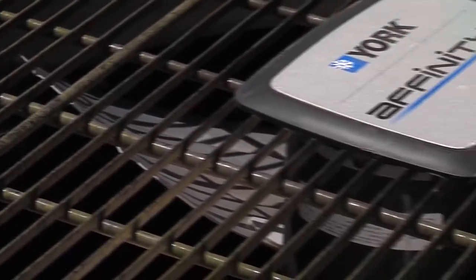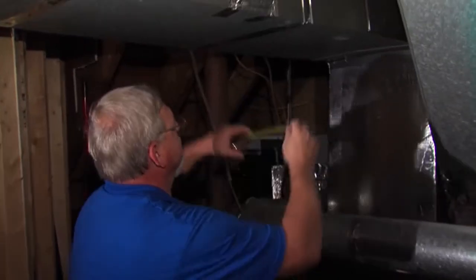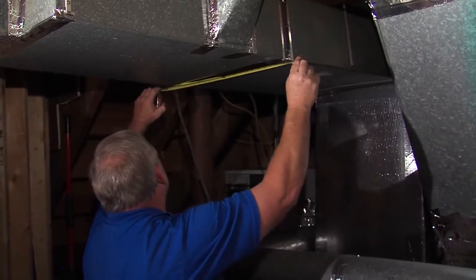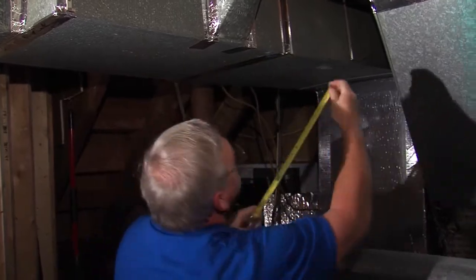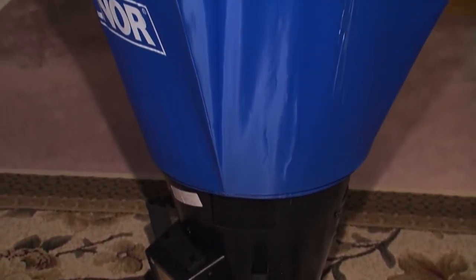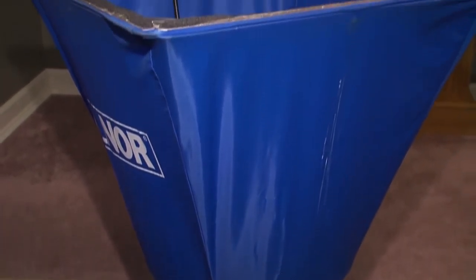He says most homeowners give most of the attention to the equipment side of the system. It's the equipment that gets the efficiency ratings, and the efficiency ratings are what are used to entice homeowners to pursue a rebate from your electric company or a tax credit from the government on your tax return, or rebates from the manufacturers. But the efficiency ratings mean nothing if your duct system can't deliver what the equipment has to offer. So Comfort Air Service uses this device, which kind of looks like a megaphone, to test the air side of your system.